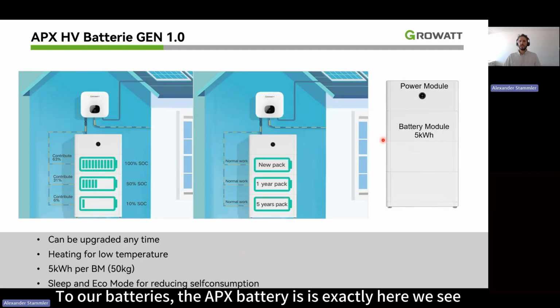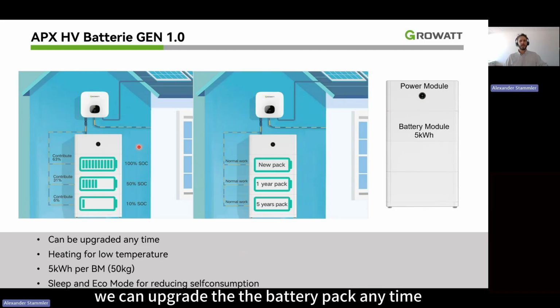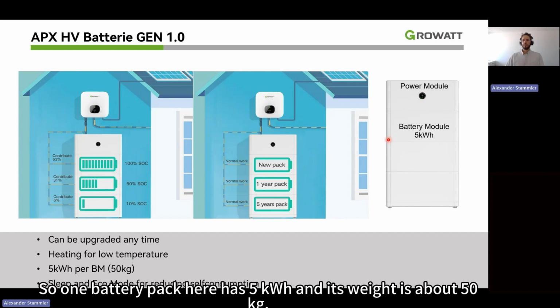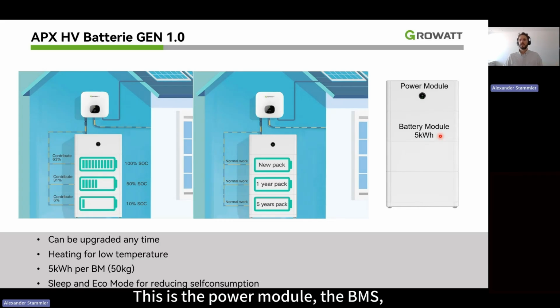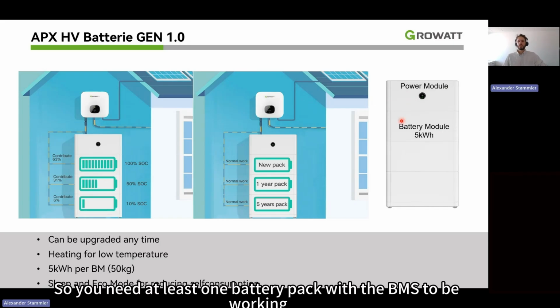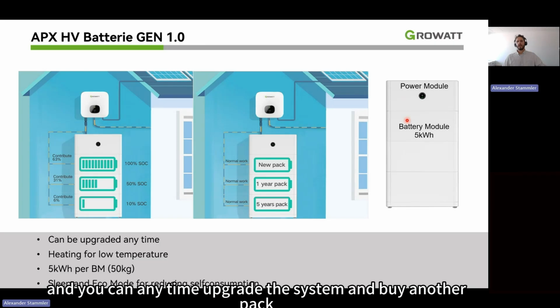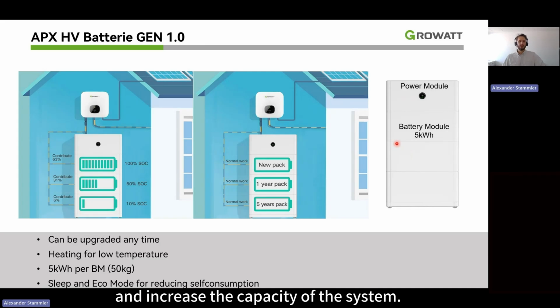To our batteries, the APX battery is exactly here. We see we can upgrade the battery pack anytime. So you can install it at first stage with only 5 kilowatt hours. One battery pack here has 5 kilowatt hours and it weighs about 50 kilos. This is the power module, the BMS, which is connected to the inverter. So you need at least 1 battery pack with the BMS to be working. And you can anytime upgrade the system and buy another pack and increase the capacity of the system.